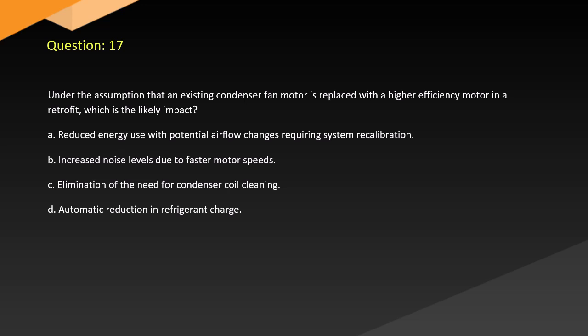Question 17. Under the assumption that an existing condenser fan motor is replaced with a higher efficiency motor in a retrofit, which is the likely impact? A. Reduced energy use with potential airflow changes requiring system recalibration. B. Increased noise levels due to faster motor speeds. C. Elimination of the need for condenser coil cleaning. D. Automatic reduction in refrigerant charge.